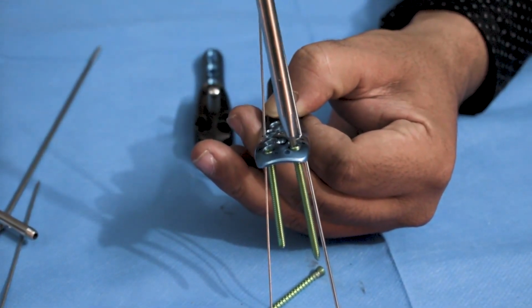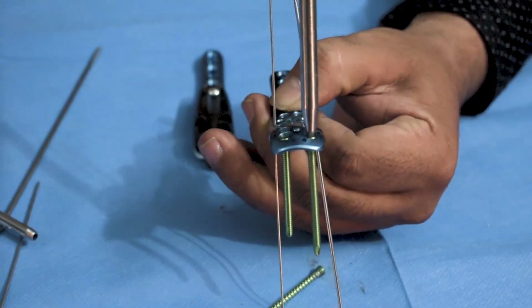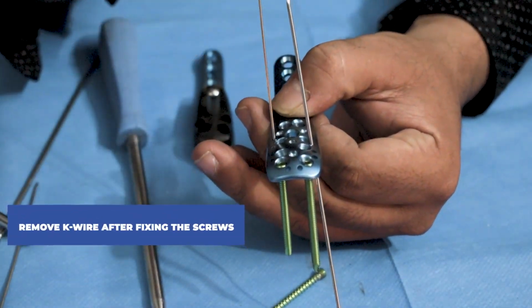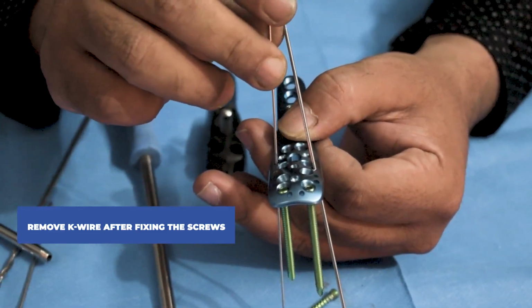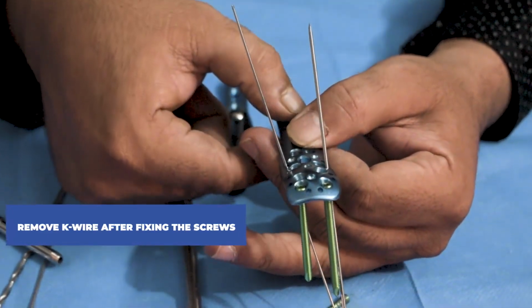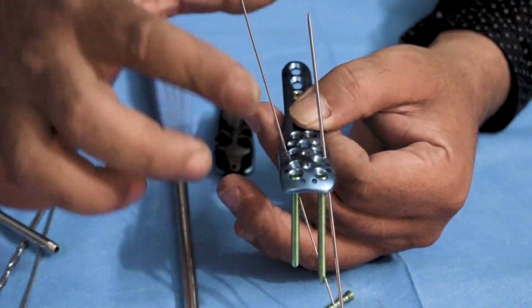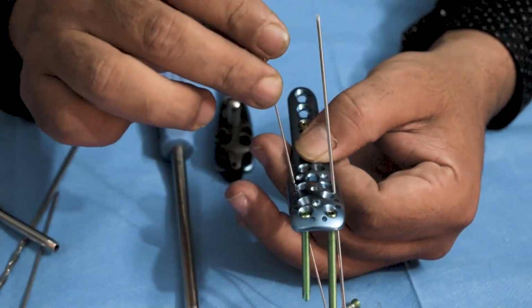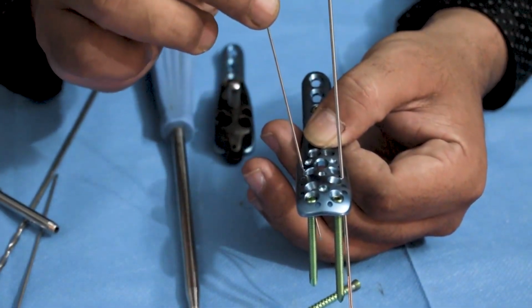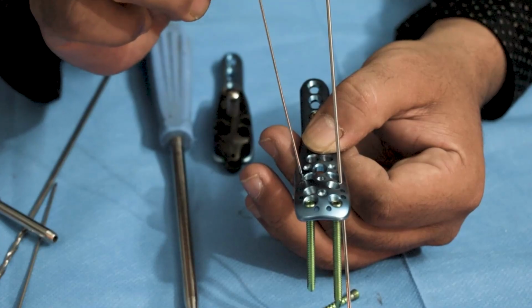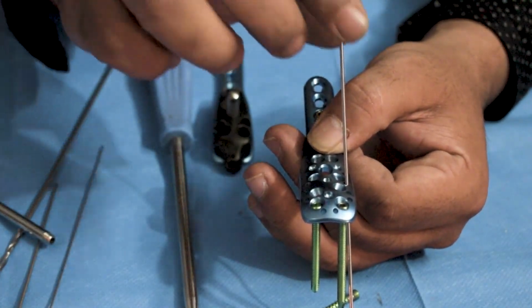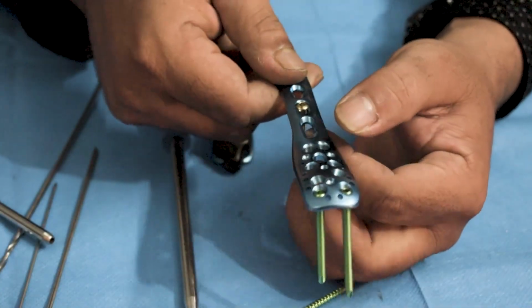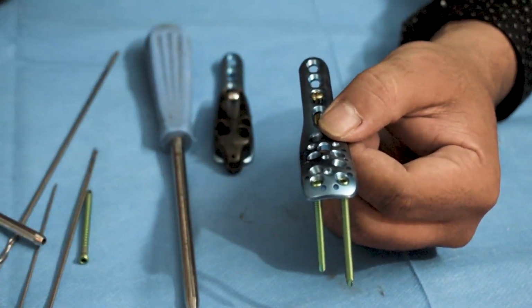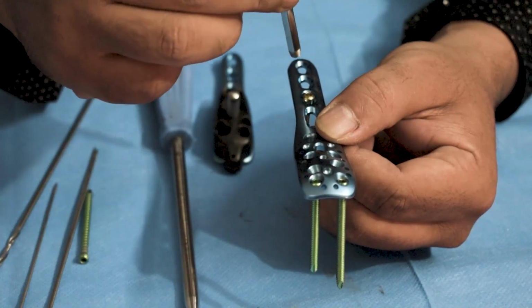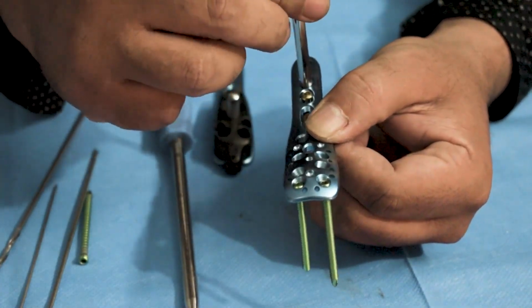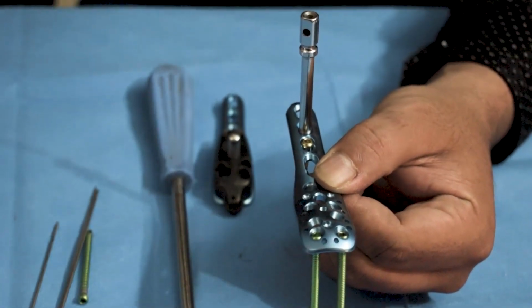Once the screws are attached and the plate is held against the fracture site, the K-wire has to be removed as soon as possible, because once the screws are tightened and the plate gets attached to the bone, it can actually bend the K-wire, which can be harmful for the patient. So once the plate is stable, remove all the K-wires from the plate. And thereafter, as per surgeon's demand, we will have to provide all the screws and fix it accordingly.